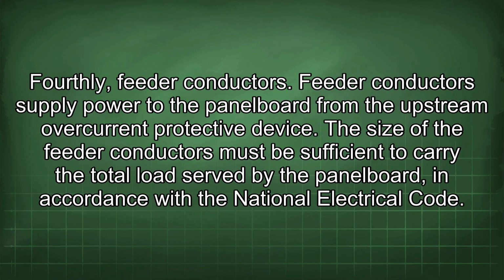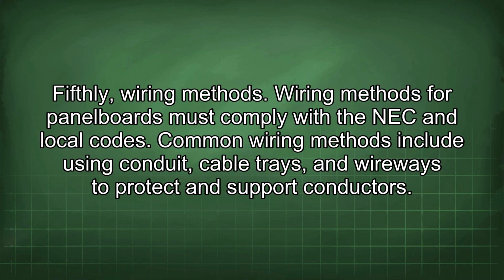Fourthly, feeder conductors. Feeder conductors supply power to the panelboard from the upstream overcurrent protective device. The size of the feeder conductors must be sufficient to carry the total load served by the panelboard, in accordance with the National Electrical Code. Fifthly, wiring methods. Wiring methods for panelboards must comply with the NEC and local codes. Common wiring methods include using conduit, cable trays, and wireways to protect and support conductors.